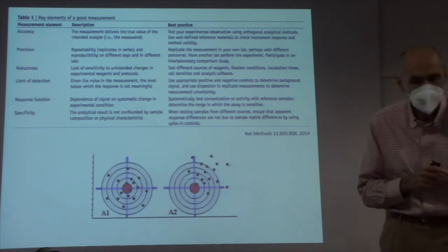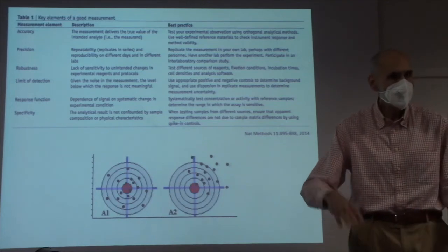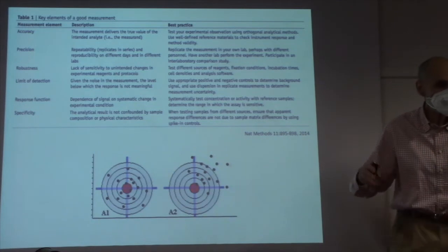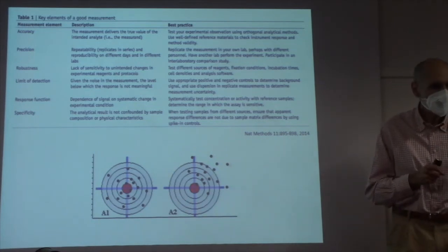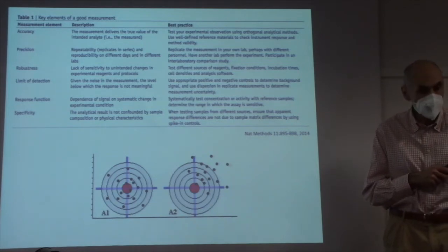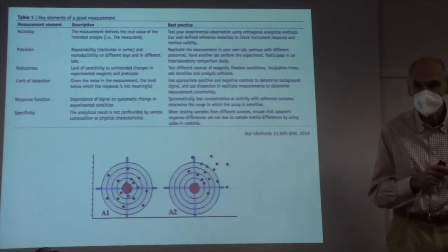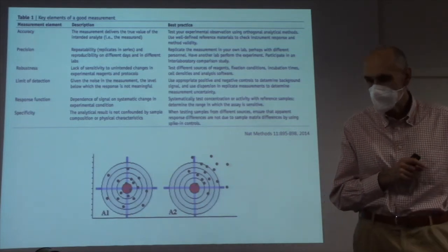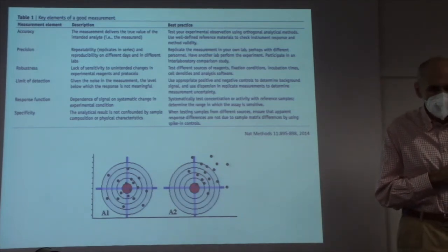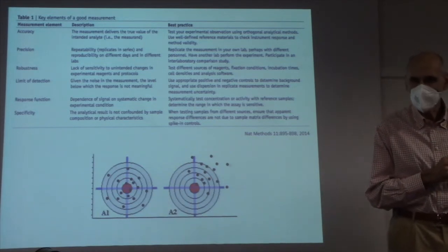If you put it on a vibrating table, say because you have a centrifuge next to it, its zero will oscillate, so you will probably get a noisy readout, and your measure will be imprecise because of this oscillation given by the vibrations. So the typical laboratory scale is not robust to vibration.